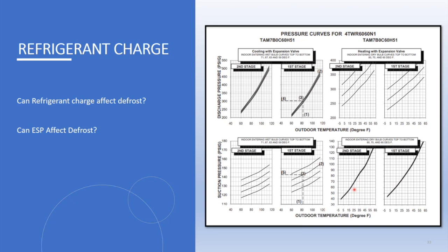If you're troubleshooting a defrost, chances are you're seeing low pressures as compared to this chart. Again, I wouldn't immediately just add some charge. Is the outdoor fan running? That's going to make your pressures really low. Is the outdoor coil really dirty? That's going to make your pressures low. Or is it frosted up? Is there ice all over the outdoor unit? And maybe you don't see it because the louvers are covering the coil.